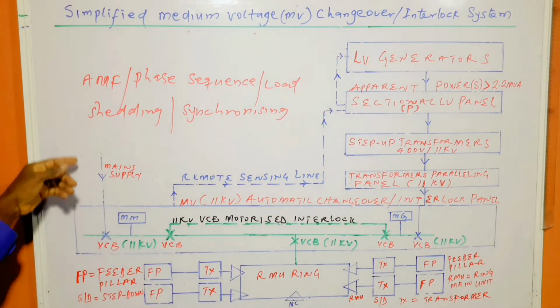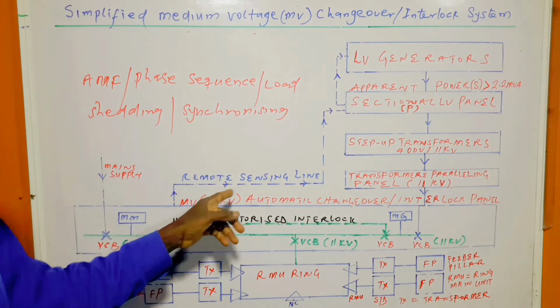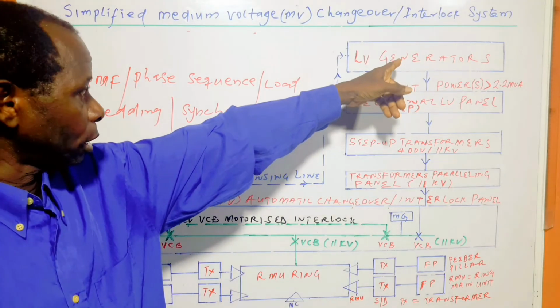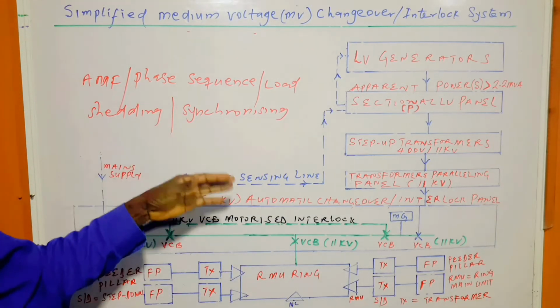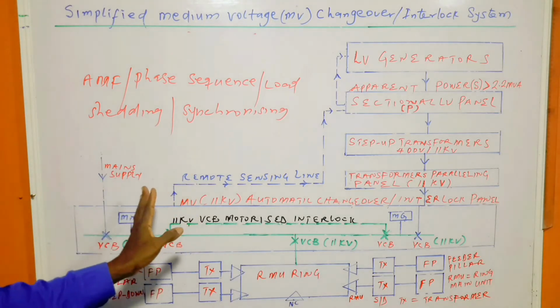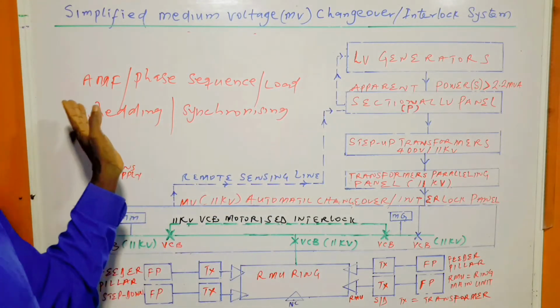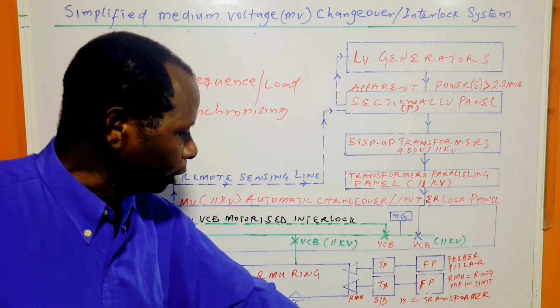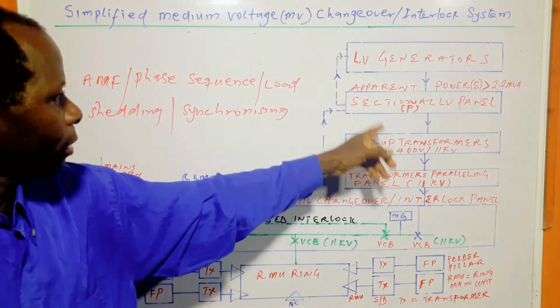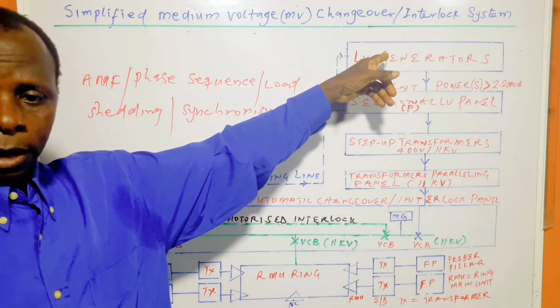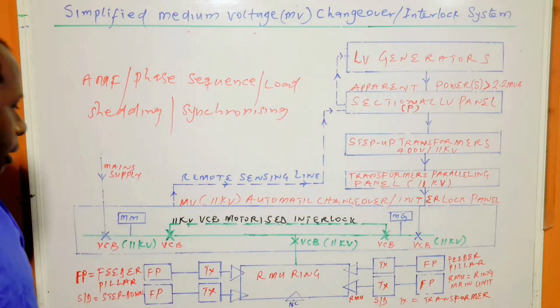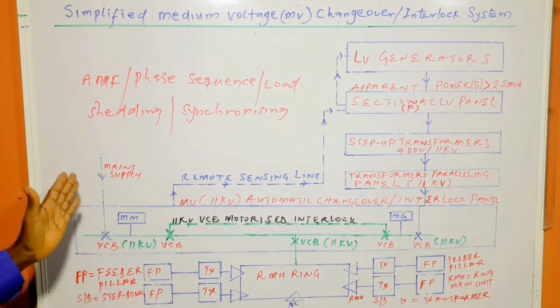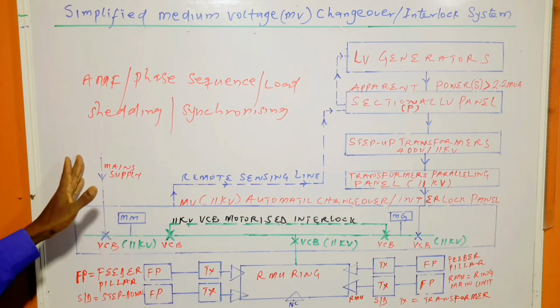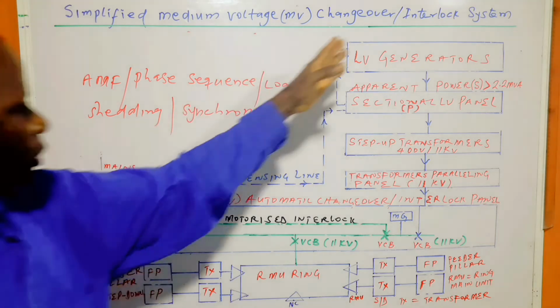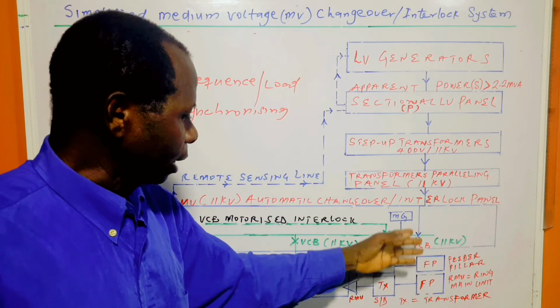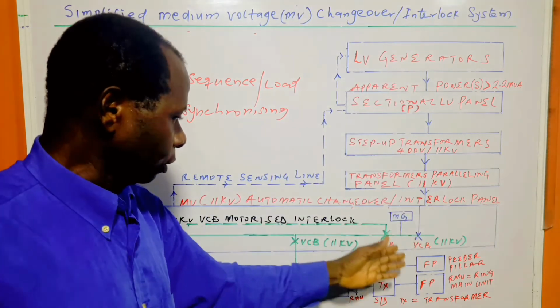When there is a mains failure here, there is signaling to it, and there is also signaling to the generators, and it also detects the phase sequence. If something is wrong with the phase sequence, this signaling will also take place, and it also determines the amount of power requirement, and through that it will determine the number of generators that will be switched on at a time. Now, when there is a mains failure, that is, there is no supply from the mains, the generator will be functioning, and the power is delivered through the generator system to the load.